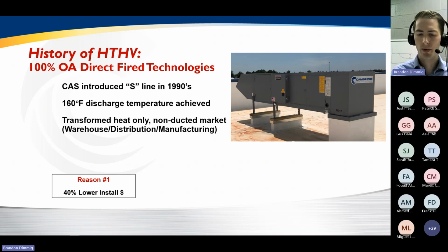And it's for three primary reasons. Number one is the lower total install cost when you look at the whole building. Historically, you throw up a bunch of unit heaters, or you'd have infrared heat, and you'd have a number of different systems in order to meet the building's heat load. But with this equipment and the high heat capacity of it, you could use fewer pieces of total equipment. And fewer pieces of equipment means fewer roof penetrations, fewer gas connections, fewer electrical hookups. And so it simplifies the overall installation of the facility and really brought that install cost down.